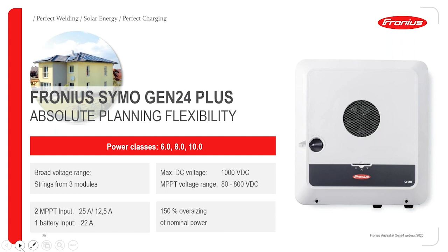Basically, what will happen is your PV, the inverter will take the power from the 15 kilowatt worth of panel. It will take 10, convert it, send it to your load, and then there's this 5 sitting there. With this particular inverter, we are able to charge directly from the PV to the battery.